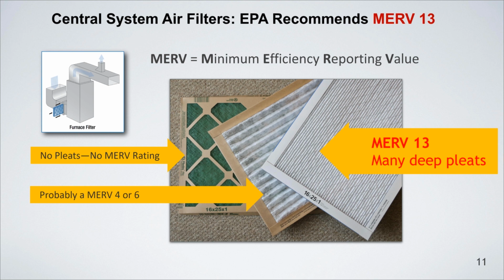One of the things that you don't want to do with any filter is crush it. And you don't want to use a filter that's too small for the frame, because then air zips around the edges. And basically you don't get any filtration at all, because air is going to take the path of least resistance, and it's going to take all the air and a lot of the particles around the filter instead of going through it. So you want to get a filter that's sized for the system that you have and fits relatively snugly, but not crushing, into the filter frame. So that's what you want if you want a furnace filter or an AC system filter, is something like a MERV 13.